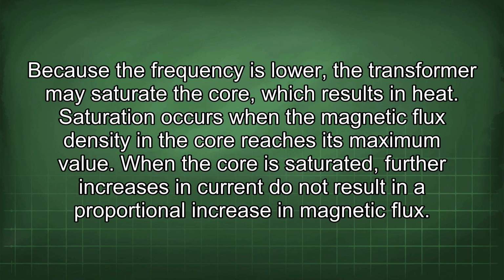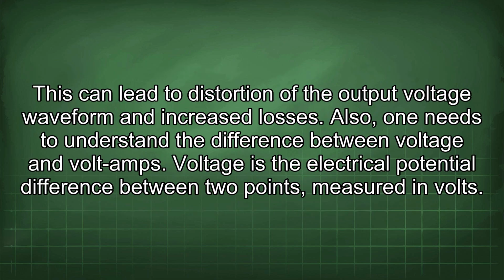Because the frequency is lower, the transformer may saturate the core, which results in heat. Saturation occurs when the magnetic flux density in the core reaches its maximum value. When the core is saturated, further increases in current do not result in a proportional increase in magnetic flux. This can lead to distortion of the output voltage waveform and increased losses.